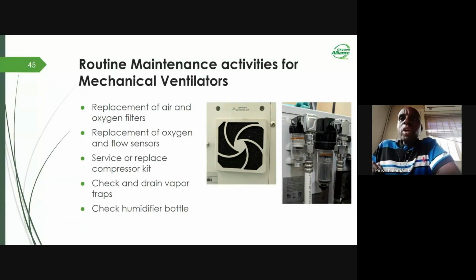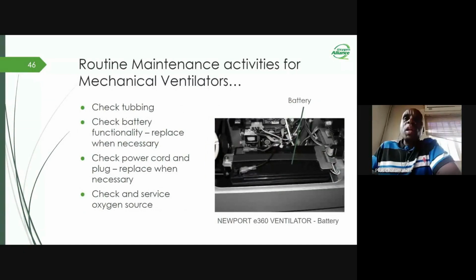On compressor kit, we are talking about the compressor that generates medical air, and also the compressor for oxygen concentrators. They also have compressors. So on compressor kit, we are talking about both. Check and drain vapor traps at the back of the machine, on the ventilator or on the compressor. Check the humidifier bottle if it is functioning properly and replace if it is possible. Check the tubings if they are intact, replace if necessary.